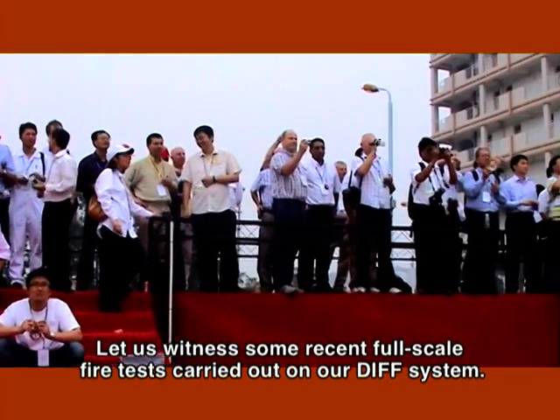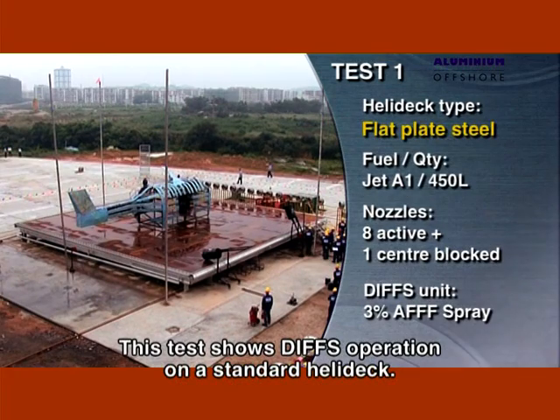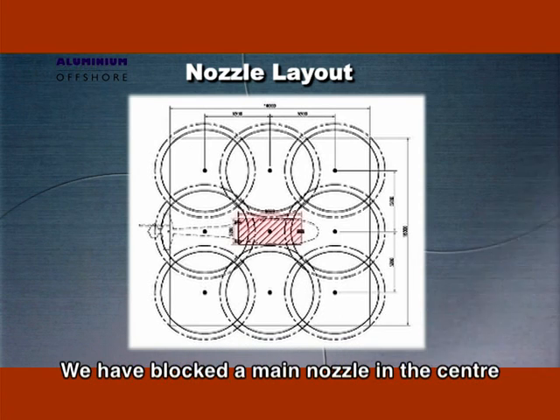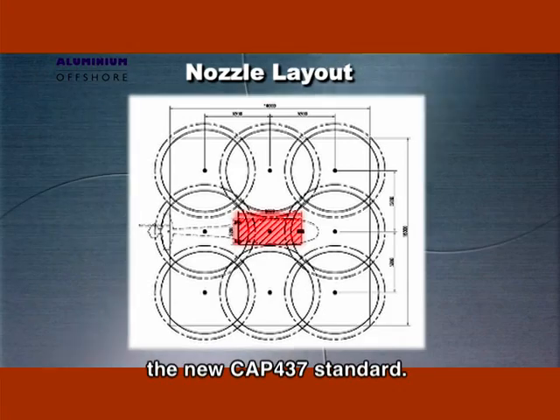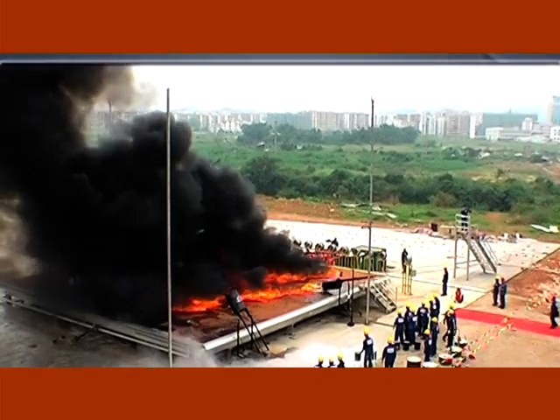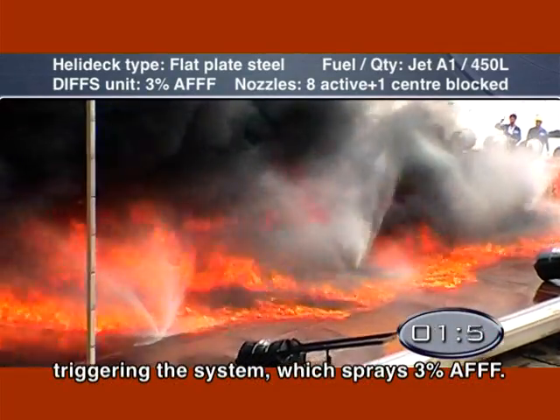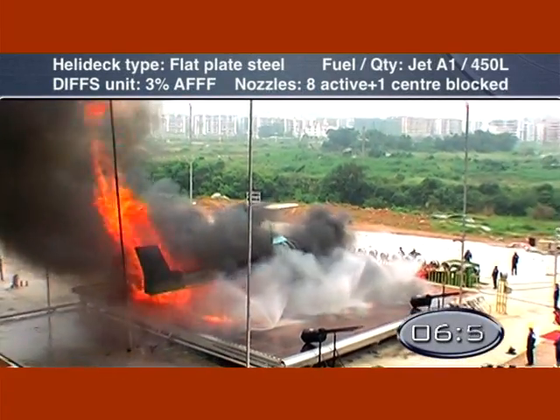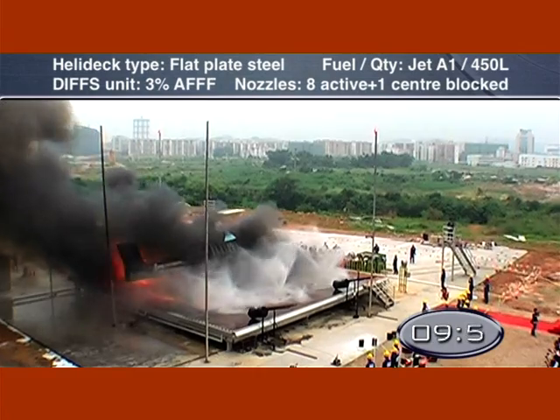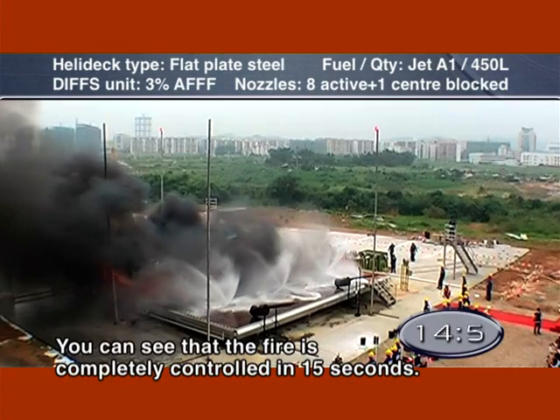Let us witness some recent full-scale fire tests carried out on our DIFFS system. This test shows DIFFS operation on a standard helideck. We have blocked a main nozzle in the centre of the helideck to allow for worst-case scenarios in accordance with the new CAP-437 standard. We will allow the fire to build up before triggering the system, which sprays 3% AFFF. You can see that the fire is completely controlled in 15 seconds.